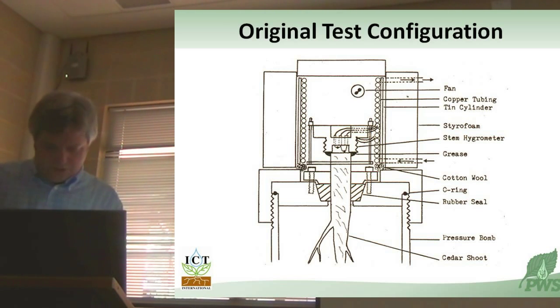You'll notice there are two thermocouples here. This is the one that makes the vapor pressure measurement - the wet bulb depression in the psychrometric context. And this one reaches out and touches the sample.